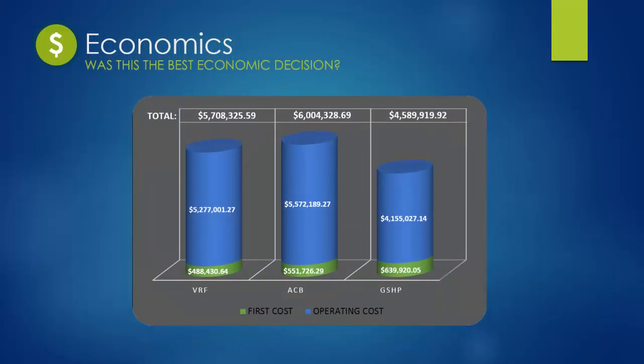A 50-year life cycle cost analysis was performed to analyze the first cost and operating cost of the three systems. First cost was calculated by comparing the differences between the systems. Variable refrigerant flow had the lowest first cost. The active chilled beam system was 13% higher, and the ground source heat pump system was 31% higher.